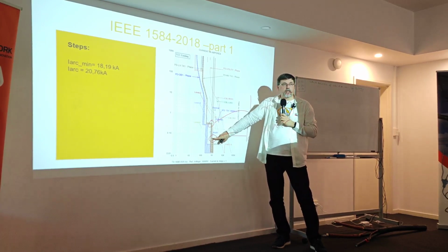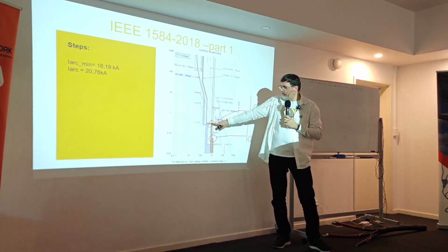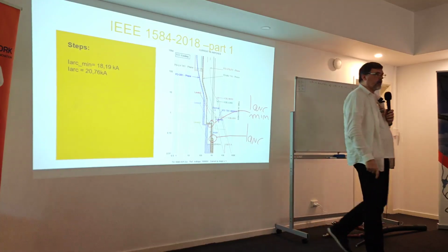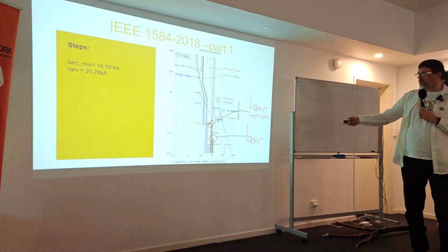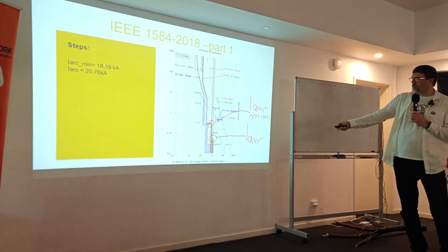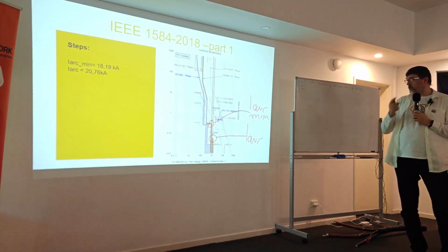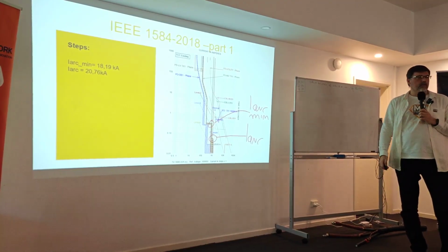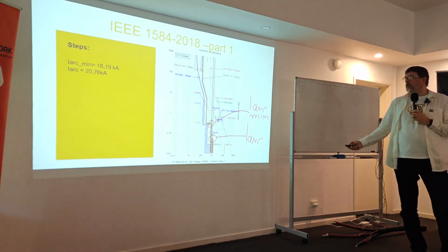So this is what we want to check. If 50 milliseconds is not too positive, maybe we have 300 milliseconds tripping time. And that's why the software is useful, so we can double check this. Okay, it's actually not 50, it's 300. This is the worst case situation that might happen for me. So that's why this minimum current is used.